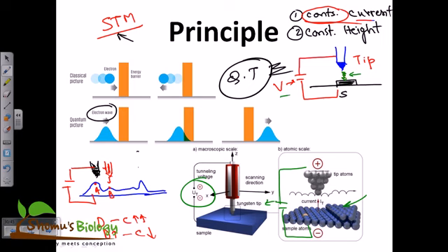Similarly, when it comes to point C, the distance becomes even more, so the tip should come much closer to again maintain that constant current. So to maintain the constant current throughout an uneven surface like this sample, the tip needs to come down sometimes and go up sometimes. Whenever it is in close proximity with the sample specimen, that data is fed to the detector.